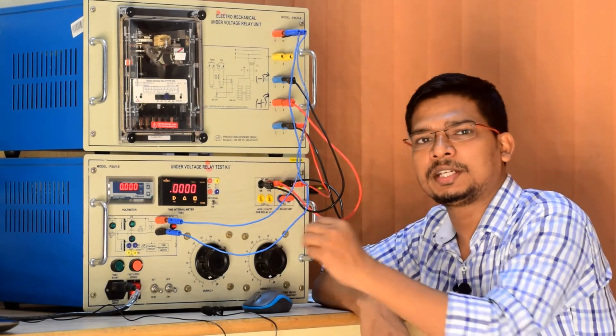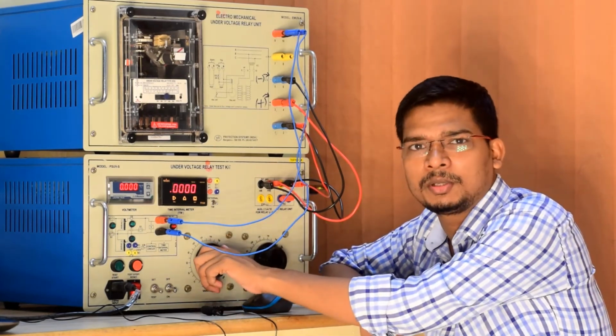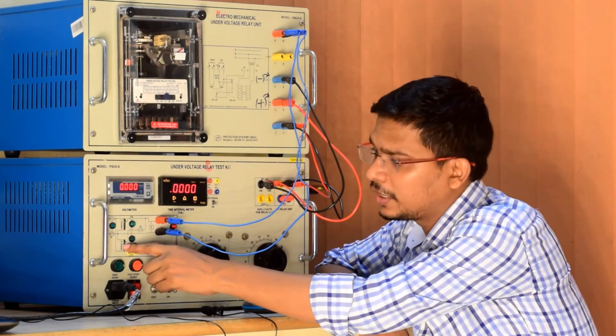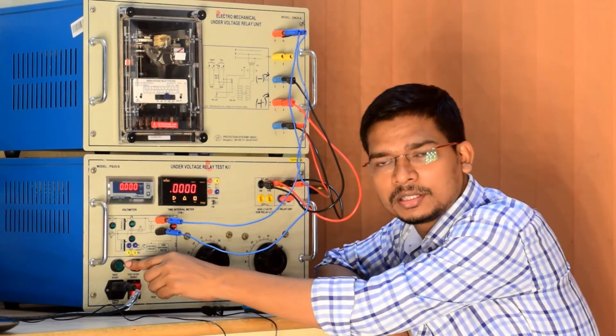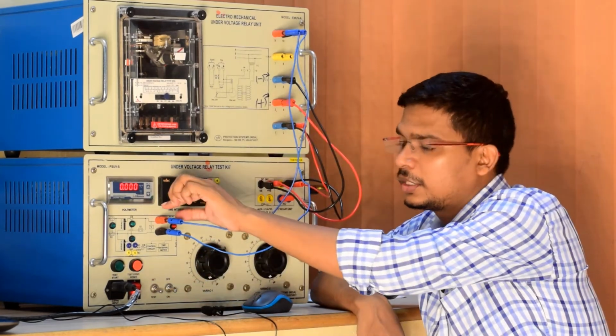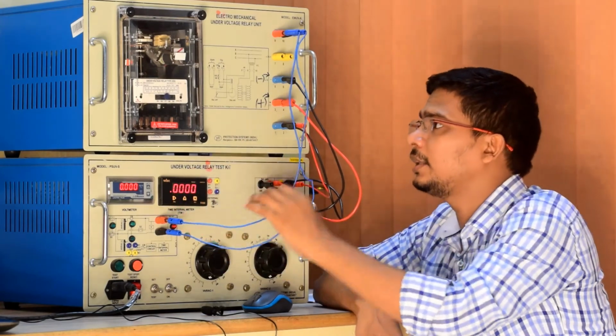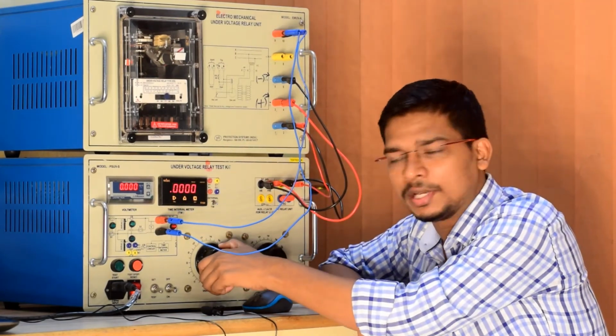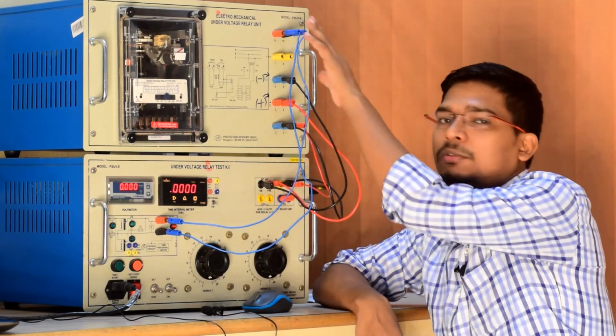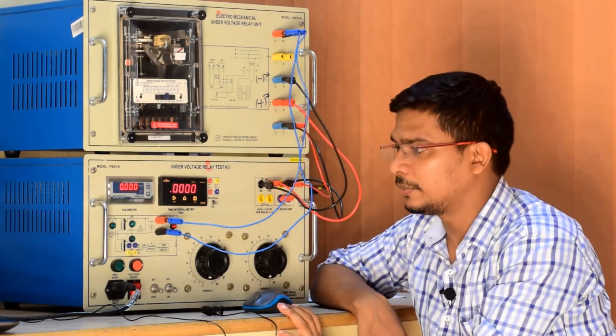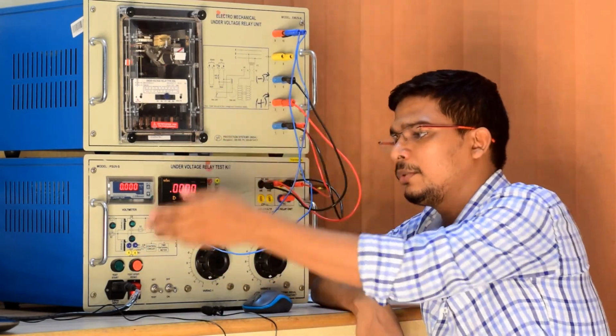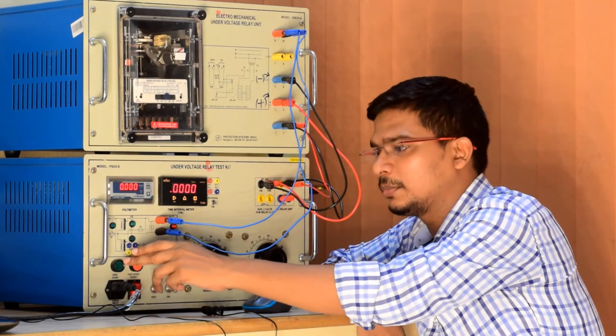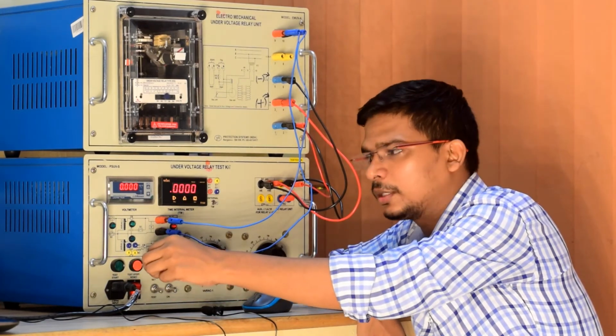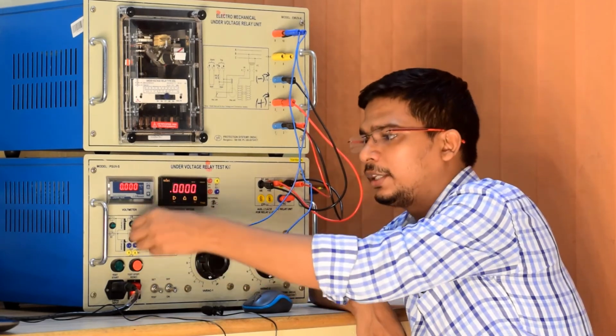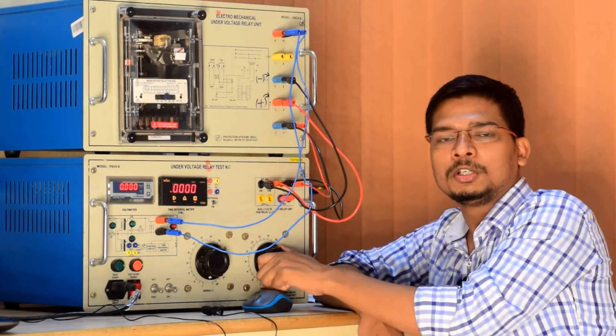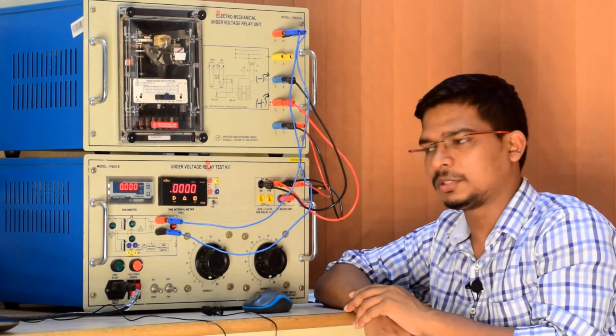For that we have to give its rated voltage, and that rated voltage we are giving from variac number 1. And also you can see variac number 1, variac number 2, two variacs are there, and before turning on the circuit breaker, variac number 1 is connected to this voltage output terminal, and this is going to the relay. So how much voltage we apply here using variac number 1, that much voltage will go to the relay terminal. That means 110 volt, from variac number 1. Then when we change the circuit breaker position, that means off to on, the variac source, earlier variac 1, will change to variac number 2. So from variac number 2 we will apply that amount of under voltage as per our observation.